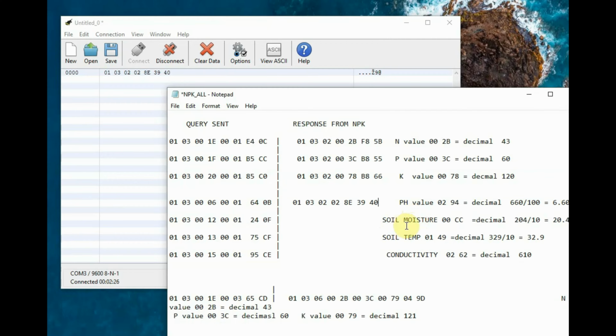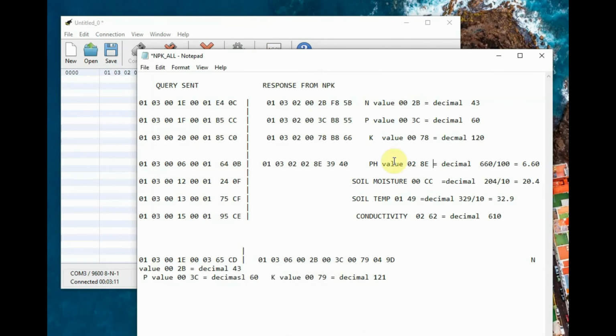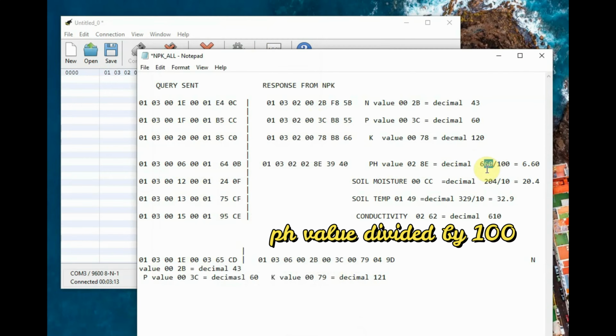Here the 4th and 5th byte has the actual pH value. This is in hex value. Converted to decimal, we get 660. As per the data sheet, this pH value should be divided by 100 to get the exact pH value. It is 0.01 pH as per the data sheet. So you have to divide it by 100. This is the pH value.